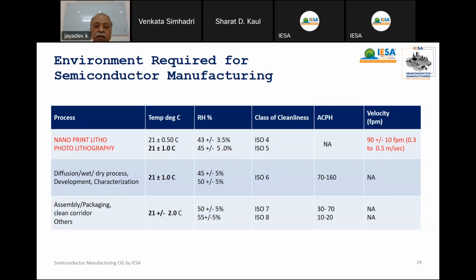You pass through the different furnaces and do different processes. Plus or minus 1 degree the temperature control. 45% to 50% RH varies. ISO 6, that is class 1000 cleanliness is required. And air change per hour as per standard varies from 70 to 160. And here velocity is not applicable. We go for packaging, other operations other than diffusion and photolithography, can go even 21, 22 degrees, 2 degrees the tolerance. 50 to 55% RH. Can go for ISO 7, ISO 8 means class 10,000 to class 1 lakh clean rooms. For ISO 7, 30 to 70 ACPH is recommended. And for ISO 8, 10 to 20 ACPH.